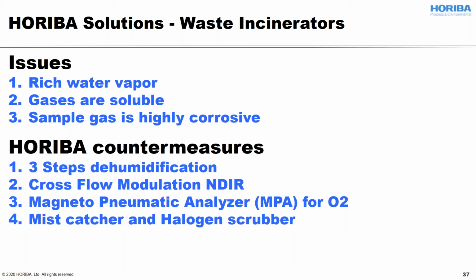Okay, let's wrap up here. The issue of waste incinerators is rich water vapor, the gases are soluble, and the sample gas is highly corrosive. The HORIBA countermeasures are three-step dehumidification, the cross-flow modulation for NDIR, and the magneto-pneumatic analyzer MPA for O2. Those technologies will prevent the corrosion, the rusting inside of the unit. And the mist catcher and halogen scrubber sample system will deal with those corrosive gases. So that is the HORIBA answer to these issues.